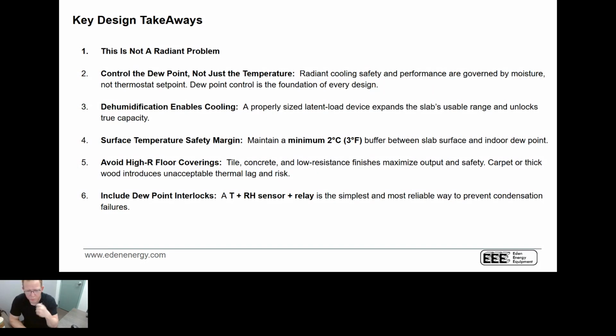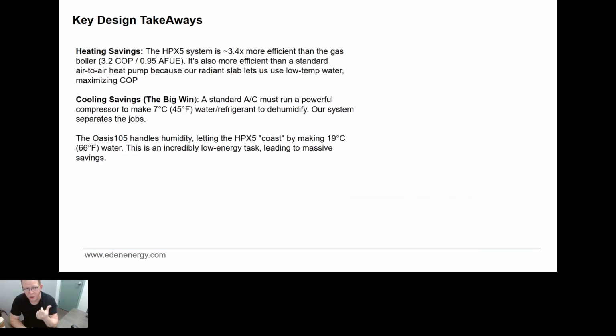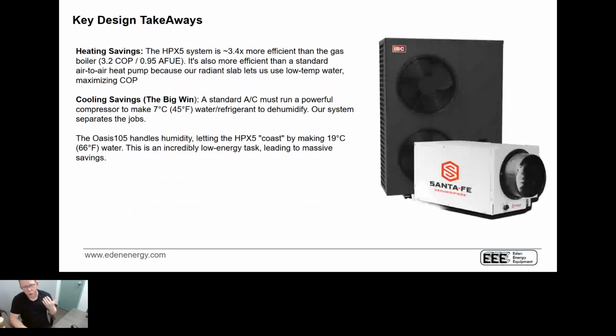We cannot put 45-degree water into that slab. In Ontario, with the humidity levels that we have at the temperatures we have, we're going to be well below the dew point. It's going to show up in a problem. Now, the cool thing is, if we do it right, if we design a system where we can do it properly, it can show up in some really cool side effects.